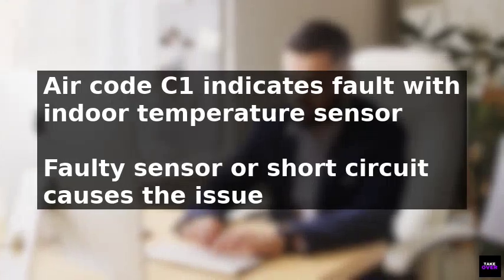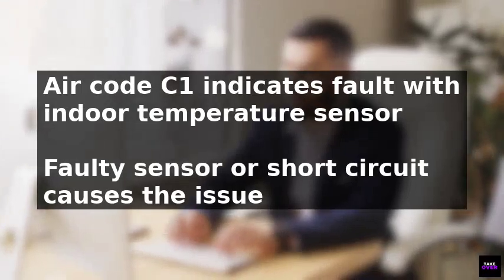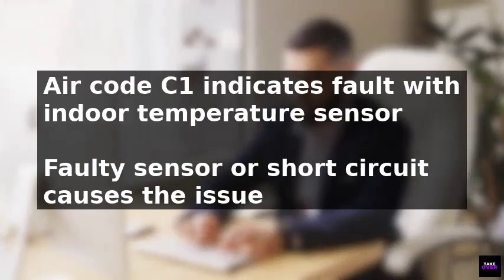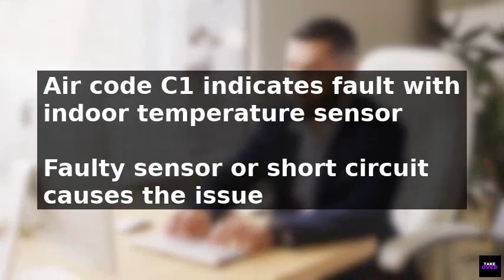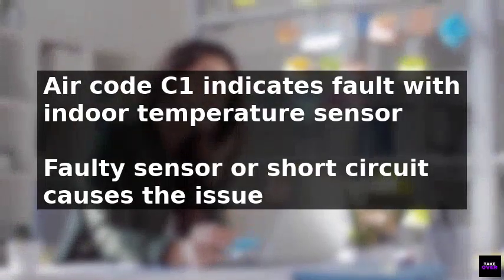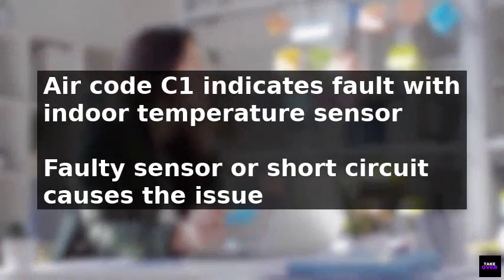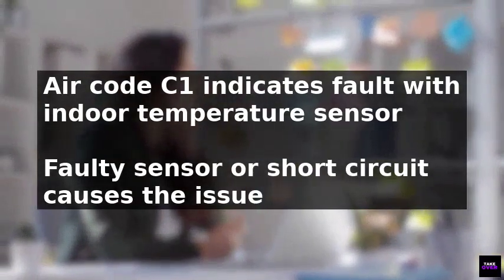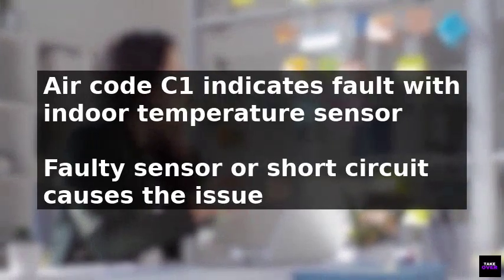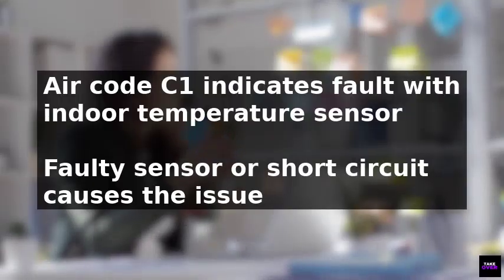The error code C1 on an air conditioner indicates a fault with the indoor temperature sensor. This issue can be caused by a faulty indoor temperature sensor or a short circuit. To fix the problem, replacing the indoor temperature sensor is a potential solution.